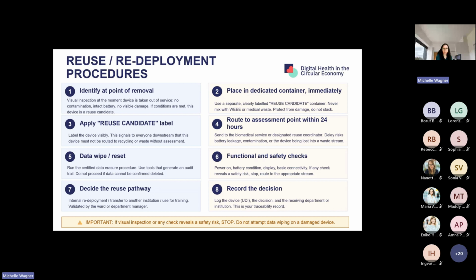So, reuse and redeployment procedures. This slide shows the operational workflow, but rather than reading through each step, I'm just going to explain the thinking behind it, if that's okay. The process is deliberately designed to prevent mistakes before they happen. Everything starts with a visual inspection. Does the device appear intact? Is there any obvious contamination? Is the battery damaged? Has anything happened that immediately suggests the device shouldn't continue its pathway? Once those initial checks have been completed, the device can move into a dedicated reuse container.